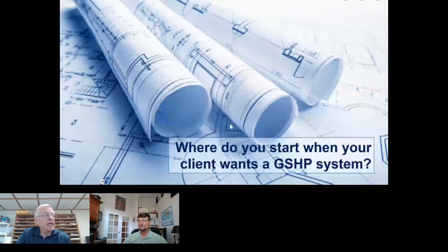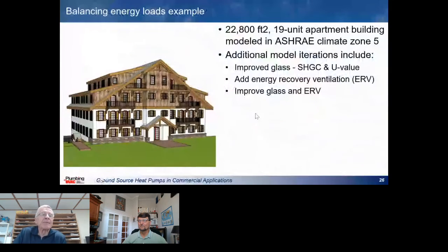So where do you start when you have a client that wants a ground source heat pump system? As an example, this is about a 22,800 square foot, 19 unit apartment building, ASHRAE Climate Zone 5, similar to Toronto. Then a couple of other iterations. The initial energy model was built based on standard building codes, ASHRAE 90.1, and several different iterations of that energy model were built. What happens if you improve the glass, change the solar heat gain coefficient, how much solar gain you're going to get coming into that window, or how much you're going to block out, and what the U value is, what the insulation level is of that glass. What happens if you add an energy recovery ventilation system and recover the energy from the exhaust air? It's going to reduce the loads in heating. It's going to reduce the loads in cooling. If you combine both of these things, you can get fairly close to balancing loads in that building.